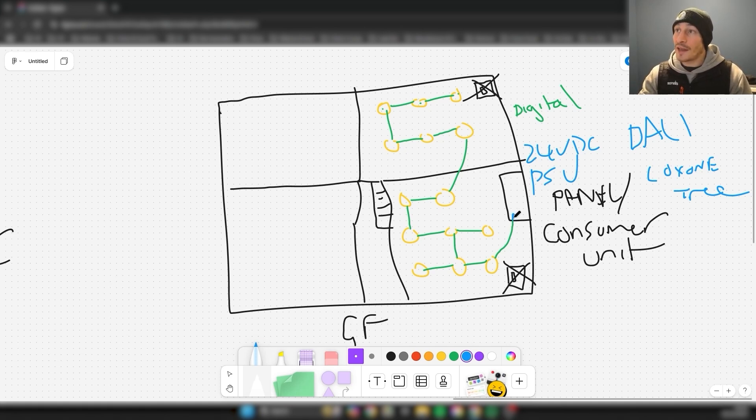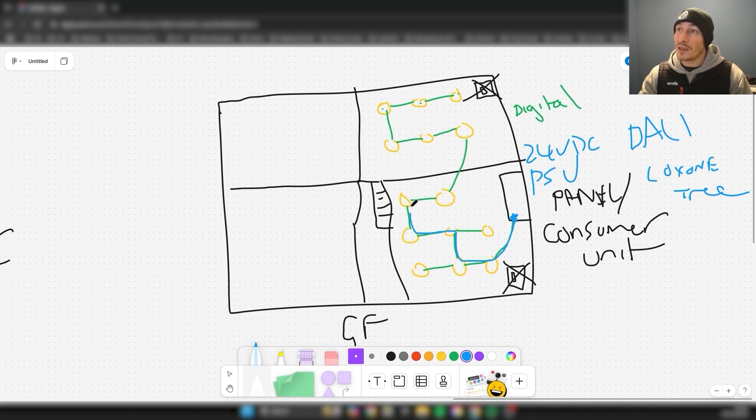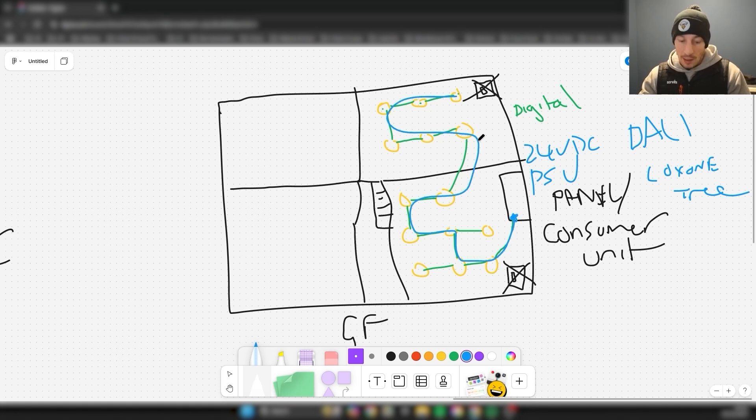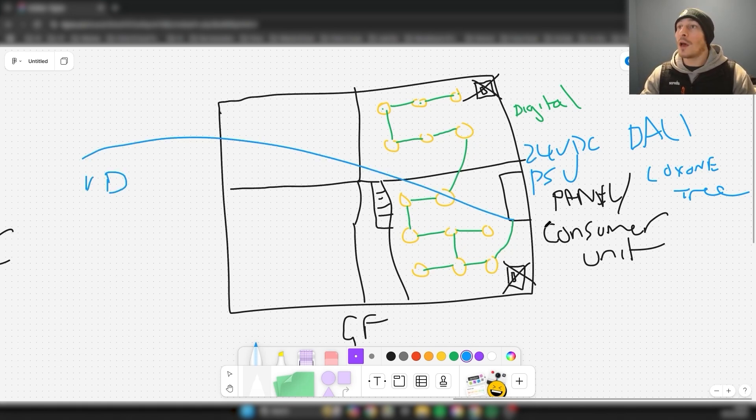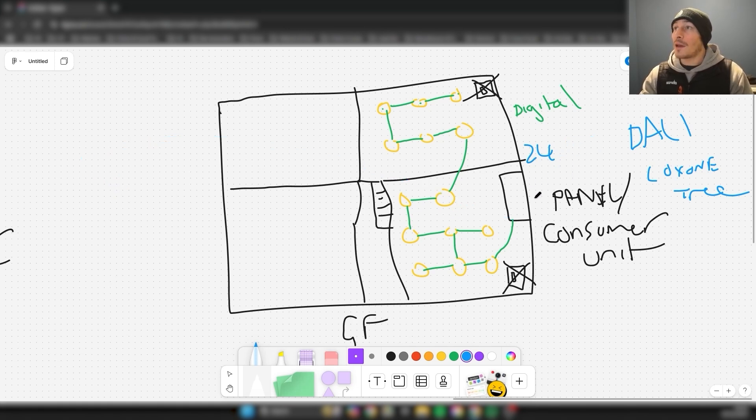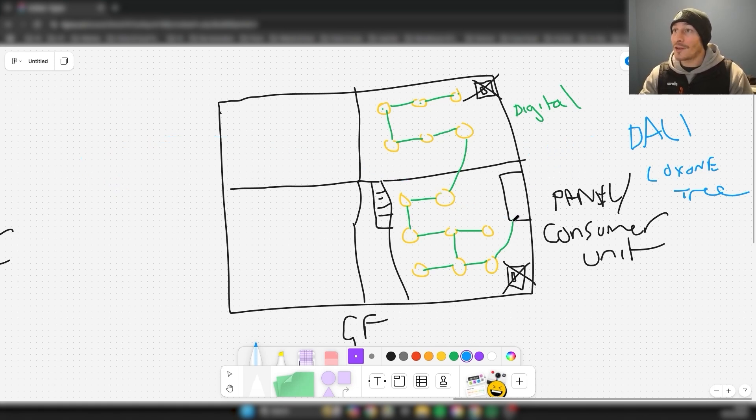You need to make sure, as you can see it's only connected at one end of the panel here, that this cable and the size of the cable can handle this load. You need to make sure that the run isn't too long so you're not getting voltage drop along this cable. These are things you need to consider.